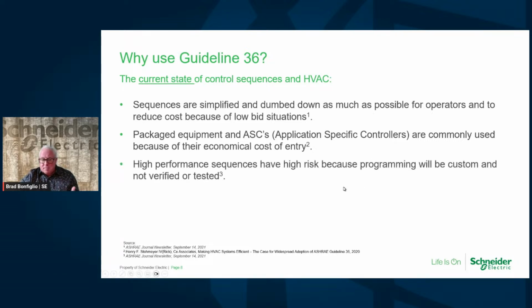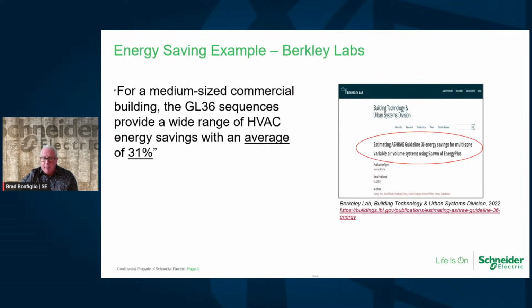The higher performance sequences in the past, they avoided that because it was custom and it was not verified and tested. The whole reason you would use Guideline 36 is they've been verified. ASHRAE has developed these as their standard. They've been tested, validated. So the idea is we can reduce that risk of using a high performance sequence, yet have it documented and tested that it works. It's still relatively unknown, which is why a lot of people don't use it, or it's too complex. So let's go through some examples of energy savings as we look at this from the industry.